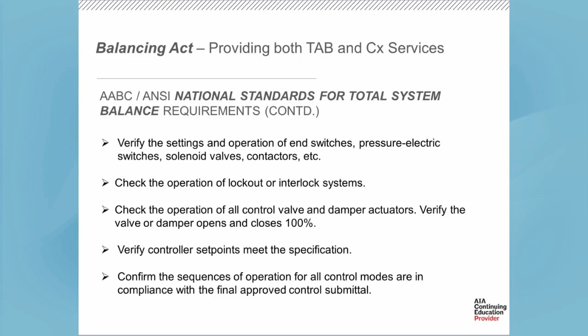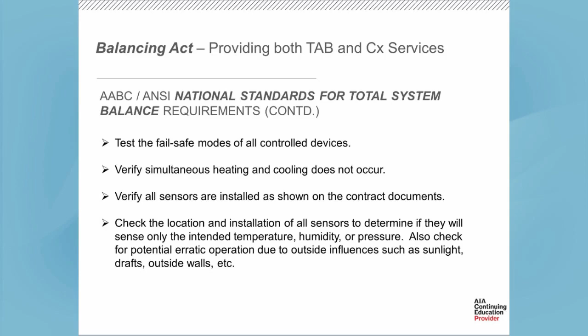So verify the settings and operation of switches, lockout and interlock systems. Some of these you're going to see are starting to overlap with things you would verify in a functional performance test, but this is what's in the standard. Check the operation of control valves and damper actuators, verify set points, and then ultimately confirm the sequences of operations for all control modes. So this is what the TAB firm is tasked with, but we're starting to see as we move along here that we're really getting into more of what we would see on the functional performance test side. So where do we draw that line? So this is just ultimately what the national standards call for from the balancing firm.